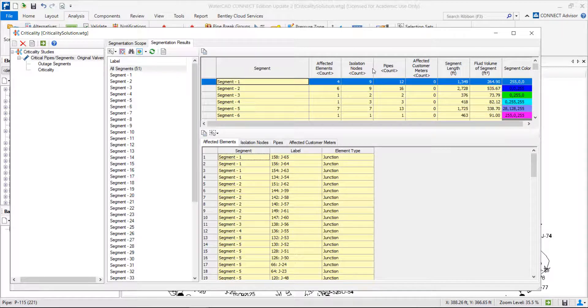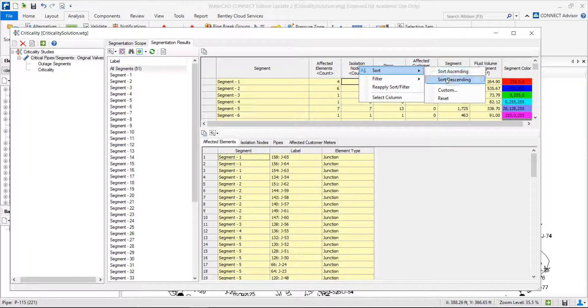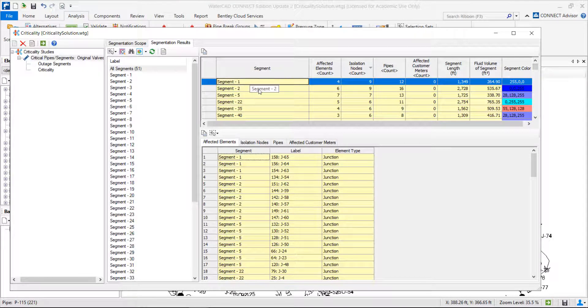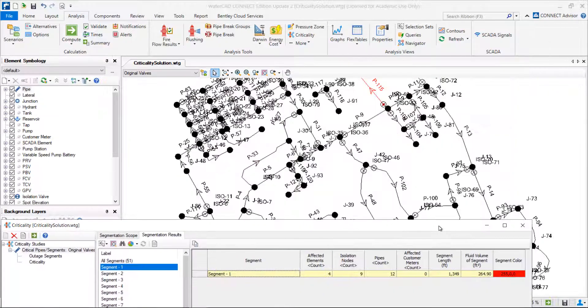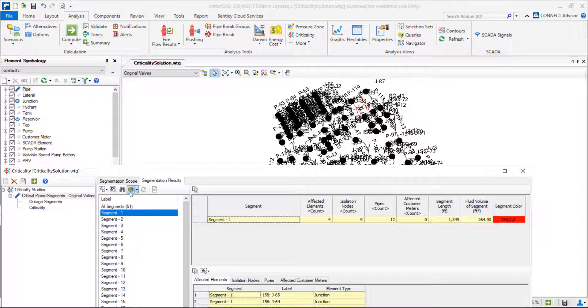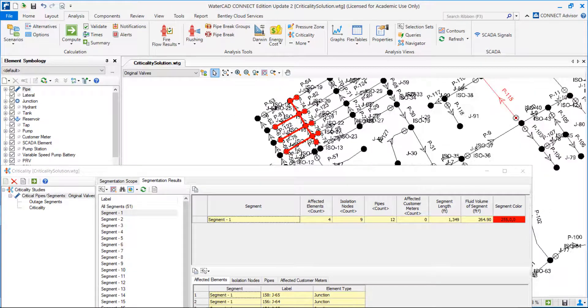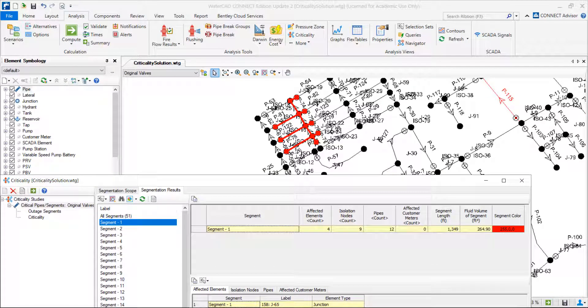I can see that on the isolation nodes column. If I sort this descending, for example, segment 1 requires me to close a lot of valves to isolate this part. Let's go to segment 1 — click on it, highlight segment. In this case, we have to close nine valves. Probably a better placement of the valves would avoid this large number of valves that we need to close.